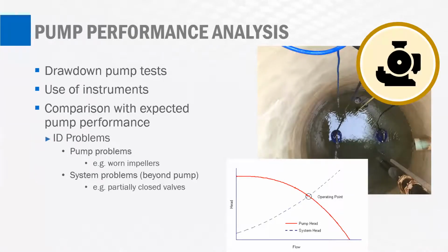Maybe it's not operating on the pump curve at all, and that dash line that you see there with the system head or system curve, maybe there's been something wrong with that system curve. You may have a combination of system problems and pump problems. But understanding where you're operating with the flow and the head is important, so that you can truly analyze, is this a pump problem? Is this a force main problem? Or is it both?